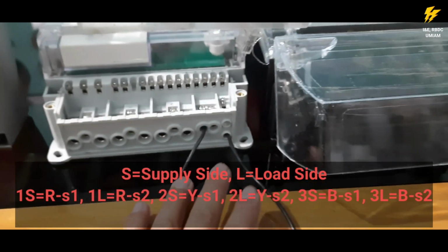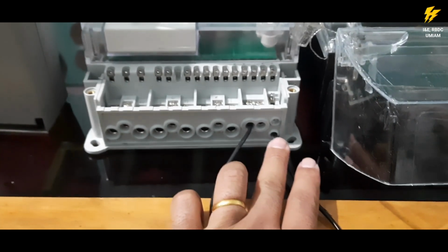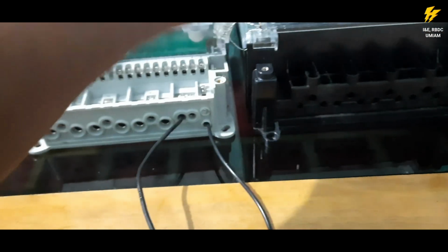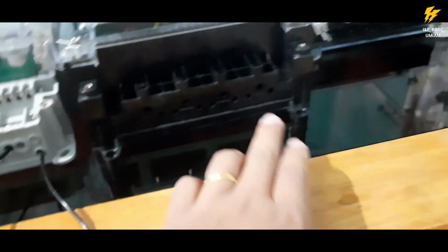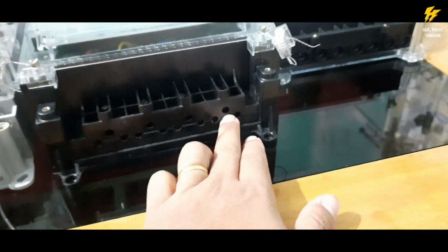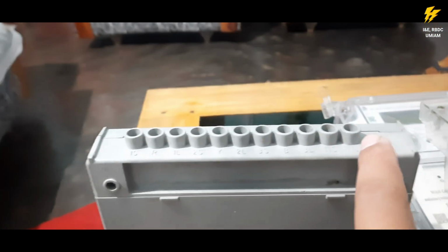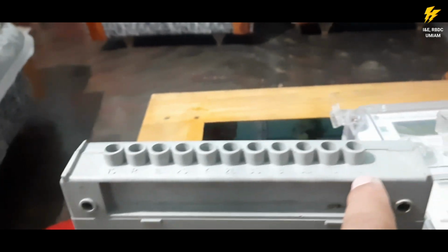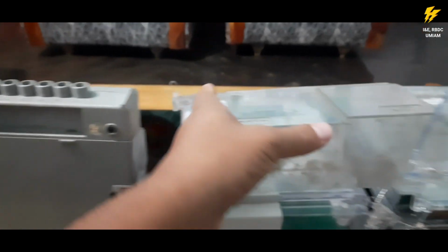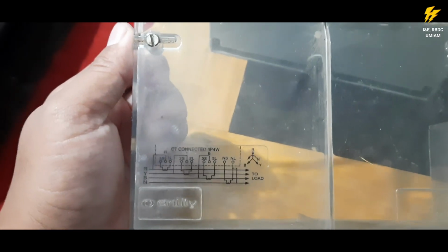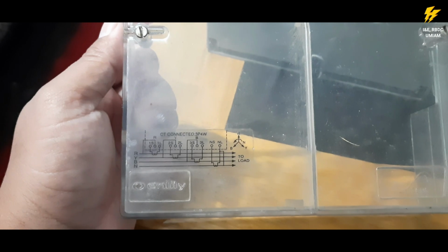Just like here, the PT supply to the neutral is a separate terminal. Here also you will have a separate terminal there. This is LTCT, it's a separate one. But this one you can give a PT supply of neutral to either L or S according to the circuit diagram given on the meter terminal cover. Every meter will have the circuit diagram, the standard circuit diagram.